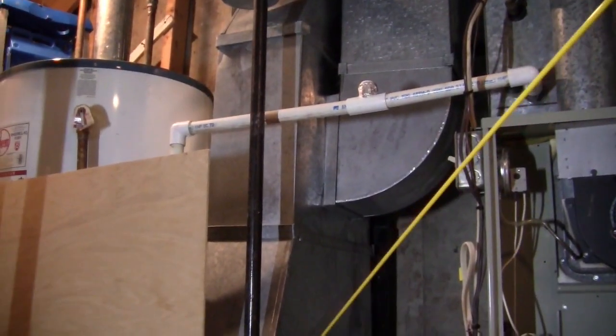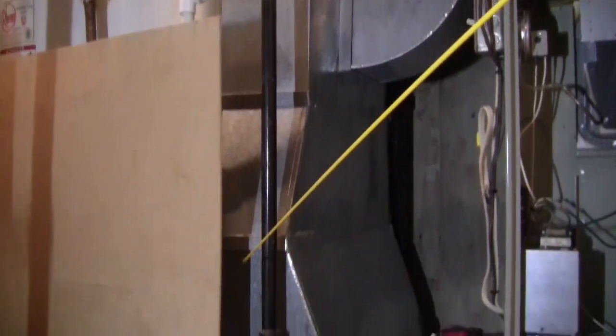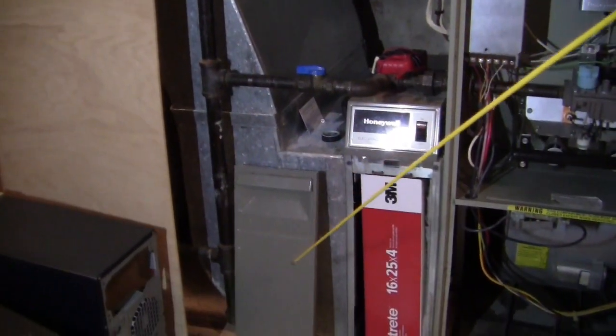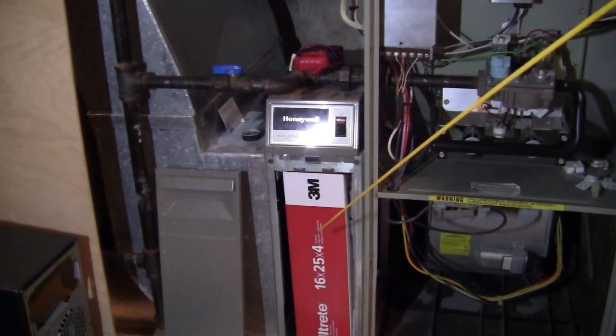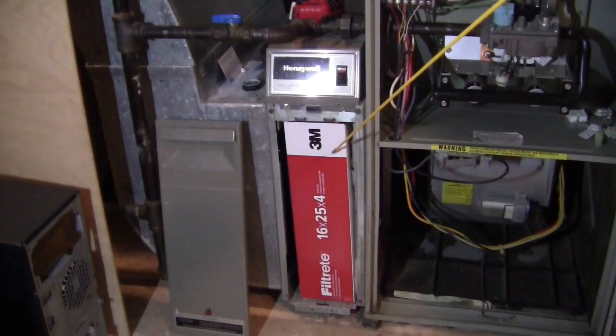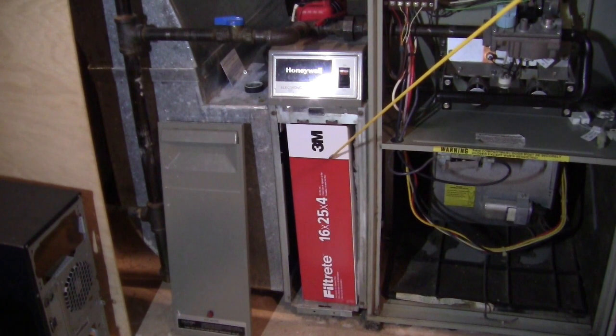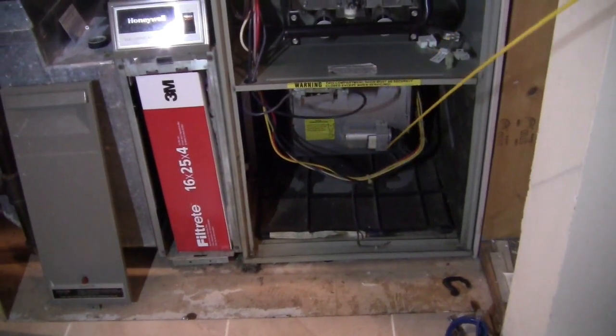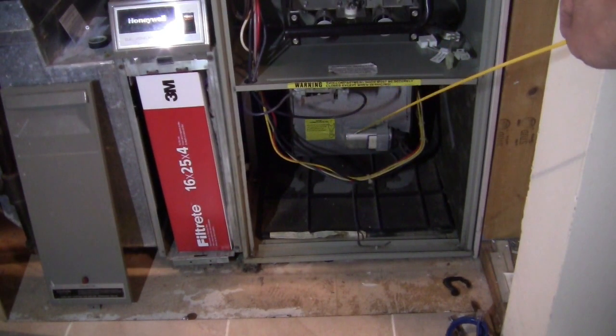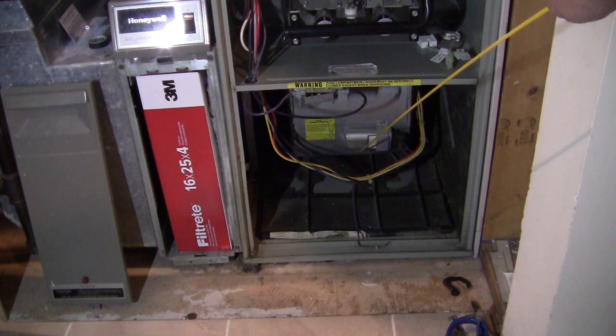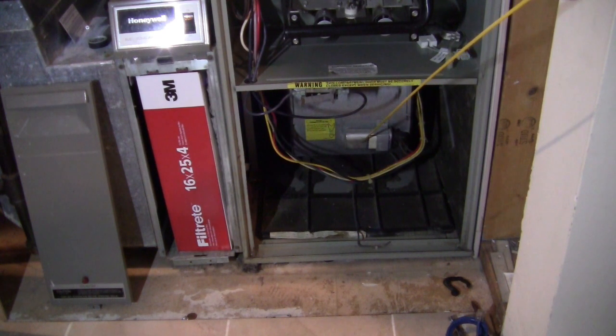The air comes from the ductwork at the top and circulates through the filter. The filter filters out the dirt or particles, anything that is trapped in the filter. And there is a motor down here. This is a big motor. There is a capacitor for the motor, and this is the part that most easily has problems. If the motor is not working, this part may be the first one you need to take a look at.